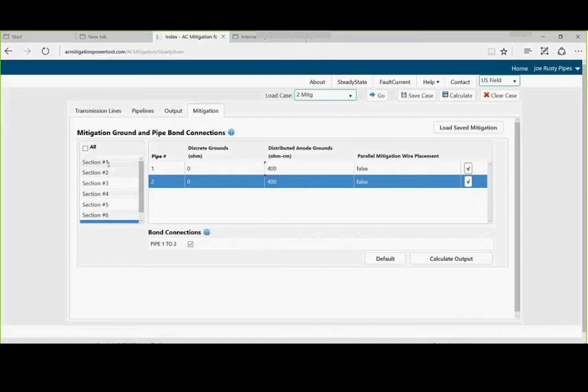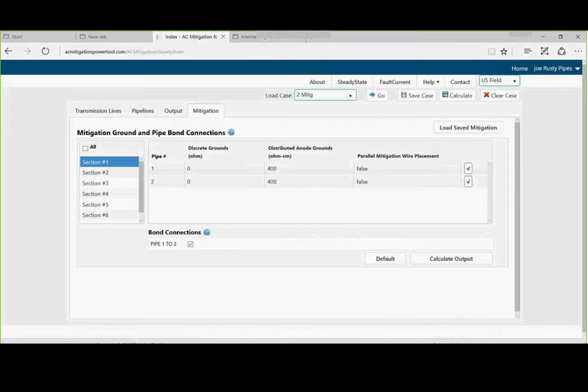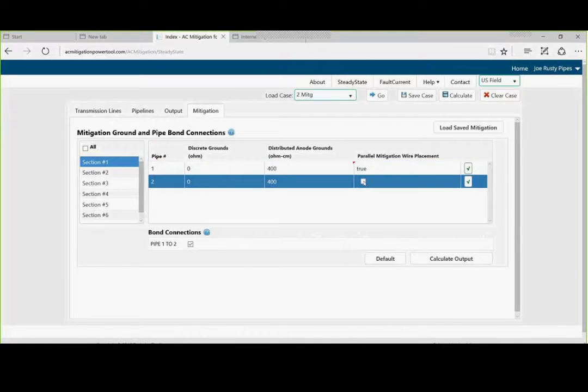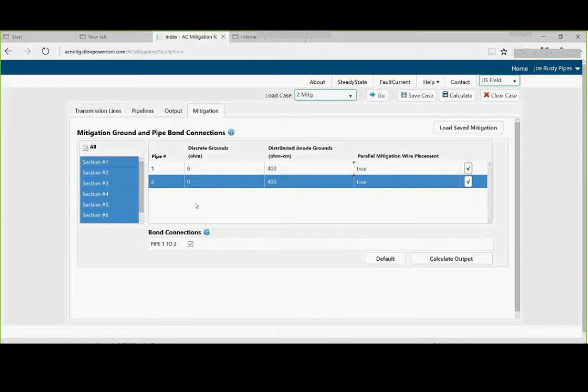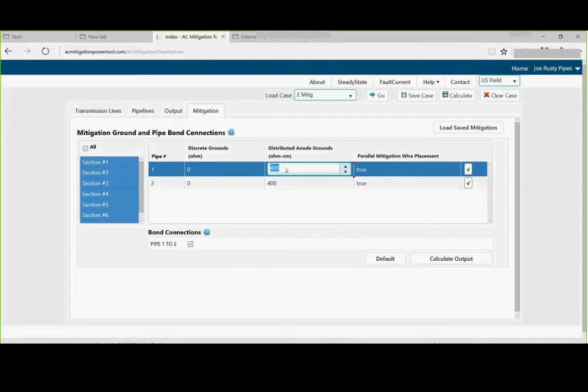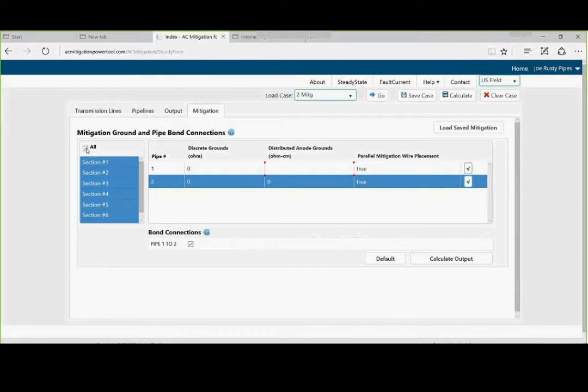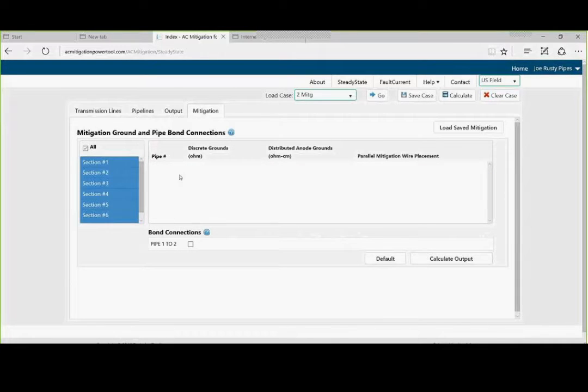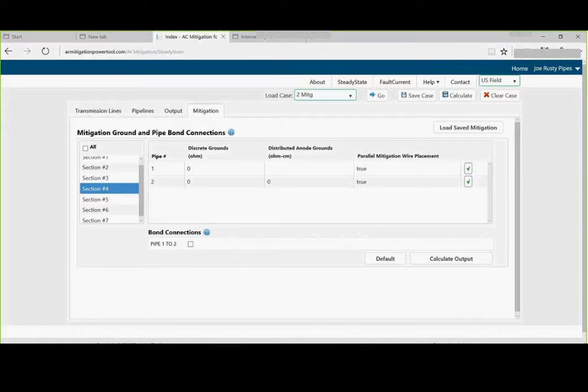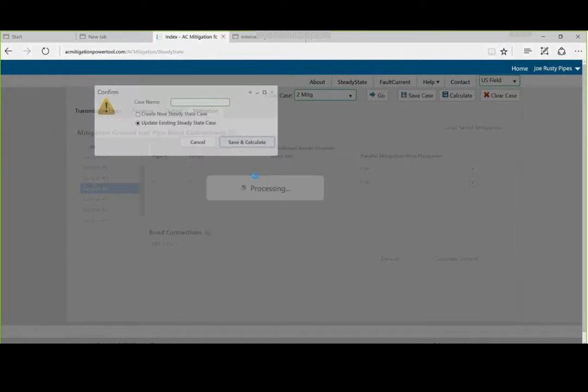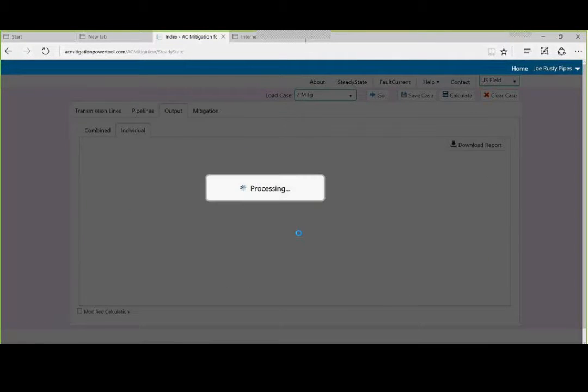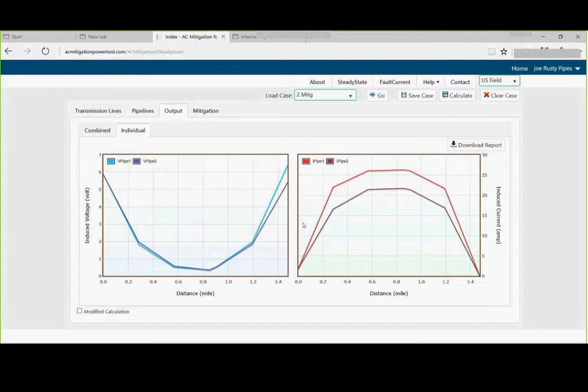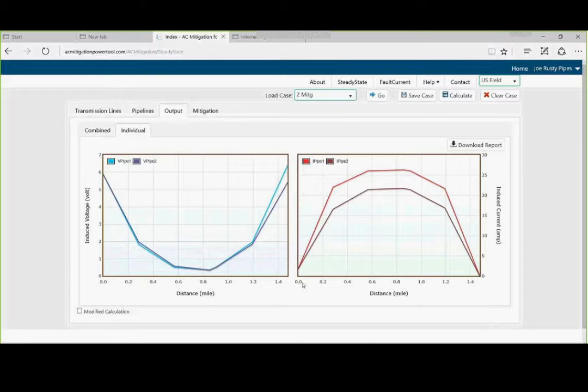And let's look at if we put a contiguous copper cable all the way for the full mile and a half. So, let's go back up to section one. And we will check this box. Check this box. And we are going to check all. And we are going to take this one out. And let's just make sure we are okay. And we will recalculate everything. And lo and behold, we have reduced the steady state voltages. From the original numbers down to about six volts.